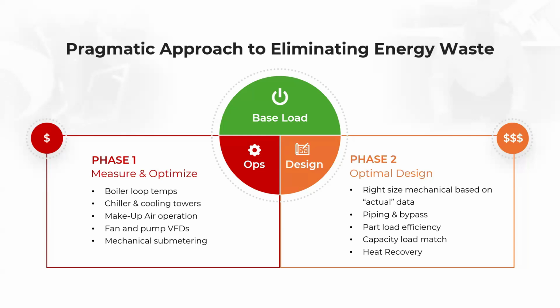And then moving into that phase 2 part where we're trying to optimize the design, some in the existing buildings where possible, and some of these only in the newer buildings if they require more major changes, but right-sizing the new mechanical systems based on the actual operating data we're seeing and not using rules of thumb for design. Getting rid of as much hydronic bypass as we can in the systems, because bypass is a real problem, both from a pumping power perspective, since every extra bit of bypass needs more consistent pumping power, but also reducing bypass helps control delta T's better, especially in cooling.